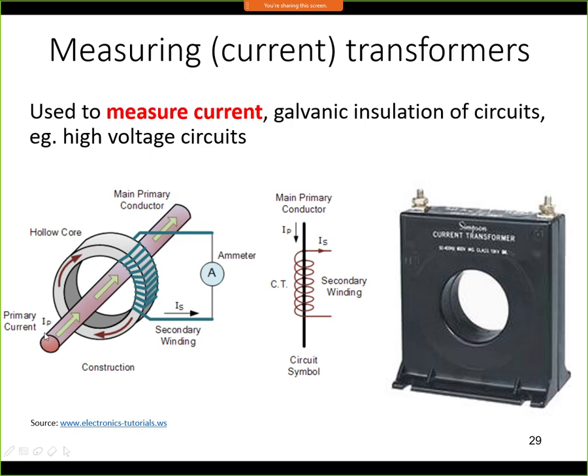In a current transformer, only magnetic coupling exists — there is no electrical connection — so it is galvanically insulated. The primary current can be in a high voltage circuit while the secondary side remains at safe low voltage. To use the current transformer, you simply slide the wire through the opening in the middle without disconnecting it. The two terminals on the secondary side connect to the ammeter. It is a safe device allowing current measurement at high voltages without removing any insulation.